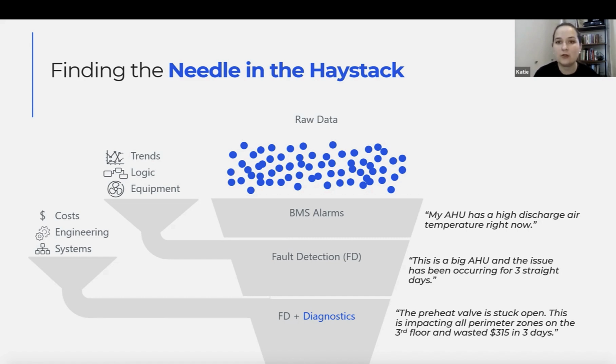Fault detection will give you another layer of information. So it lays on top of your BMS system. It pulls in information and data from your BMS and maybe some other potential data sources such as your metering systems or your lighting systems. It pulls it all into one. And then it will also pull in historical information and the logic that's written within your building automation system. So any of those sequences of operations, your FDD system, that colleague, knows that information in real time. And then it also knows the type of equipment you have. So instead of just telling you your air handler has a high discharge air temperature, it tells you the air handler has a problem that's been occurring for 3 straight days. And it's a big air handler. So it's one you might want to pay attention to.